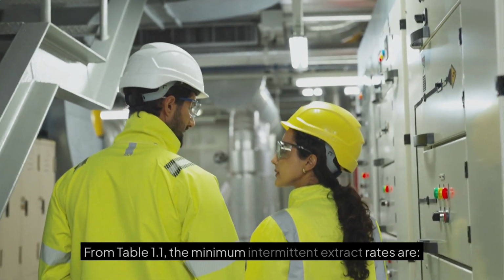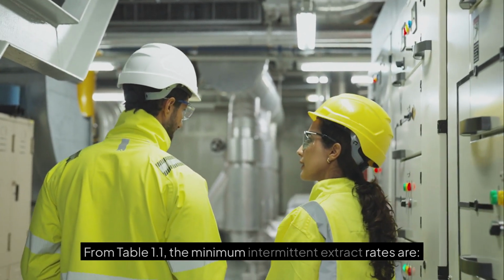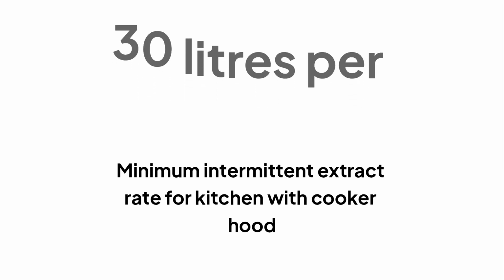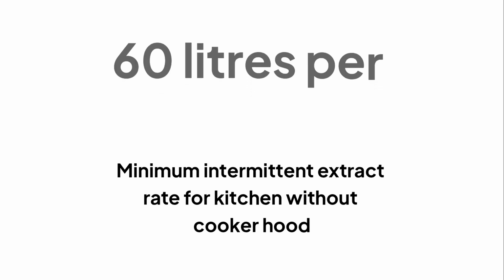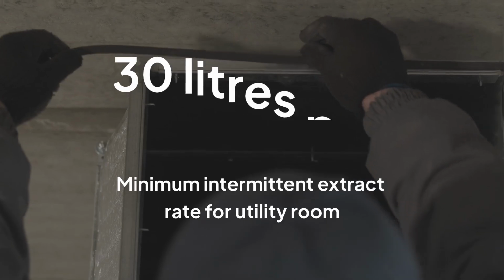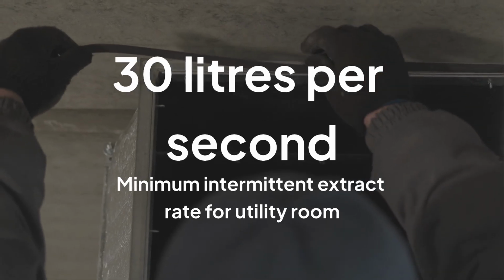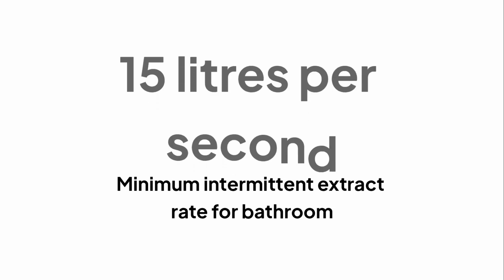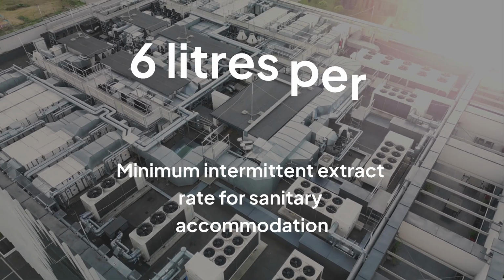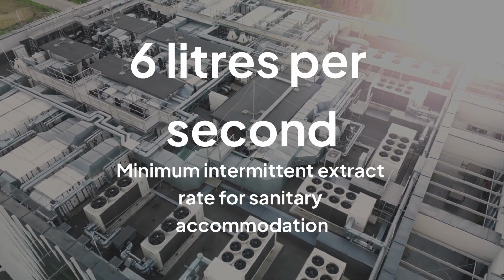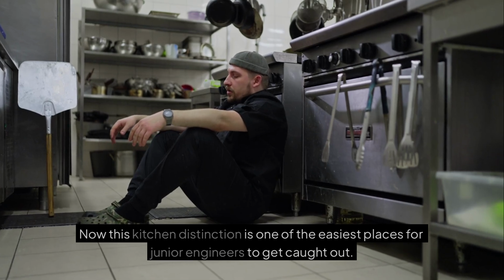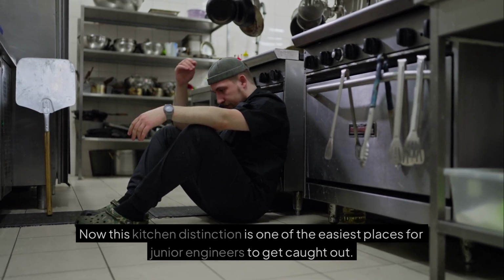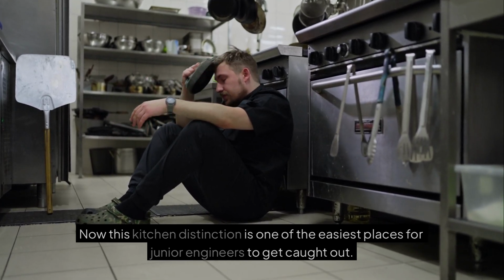From table 1.1, the minimum intermittent extract rates are 30 litres per second for a kitchen with a cooker hood extracting to the outside, 60 litres per second for a kitchen with no cooker hood extracting to the outside, 30 litres per second for a utility room, 15 litres per second for a bathroom, 6 litres per second for sanitary accommodation. Now this kitchen distinction is one of the easiest places for junior engineers to get caught out.